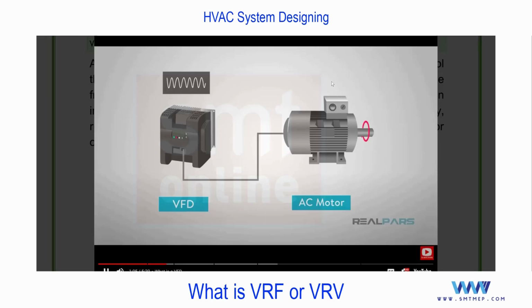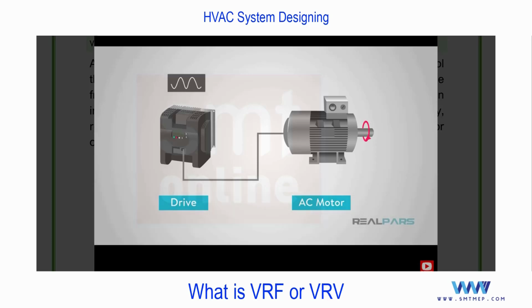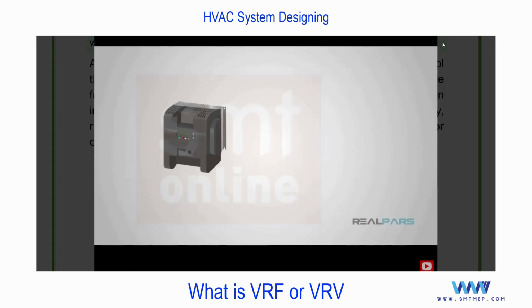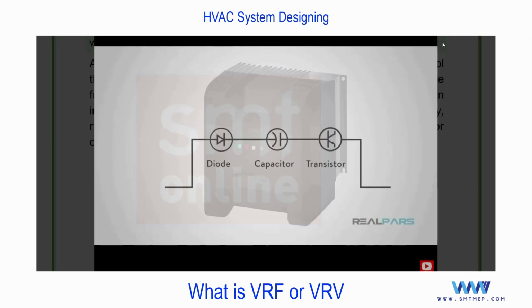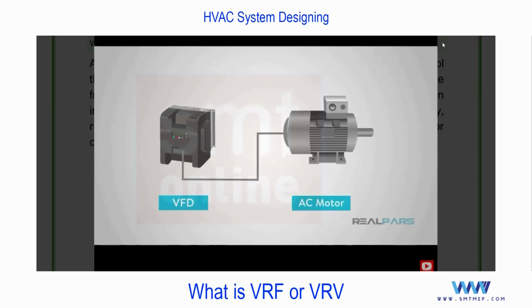You see, for example, at this level, we are talking about VRF now. So you can consider instead of motor, you can consider this as pump. Sorry, this is compressor. Some people simply call them drives. They work by adjusting the frequency of the motor to adjust the RPMs. To do this, a VFD will actually convert the voltage twice. First, it converts our three-phase AC to DC. This is accomplished with diodes. Then it cleans the DC with a capacitor. Next, it will convert the DC to AC. This is accomplished with transistors acting as switches. Utilizing these switches is what allows the VFD to adjust the frequency that the VFD supplies to the motor. This in turn controls the speed of the motor.